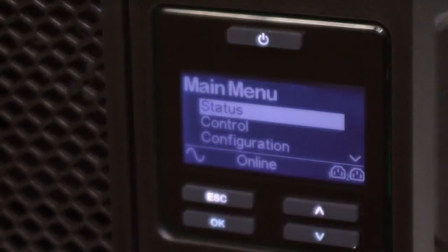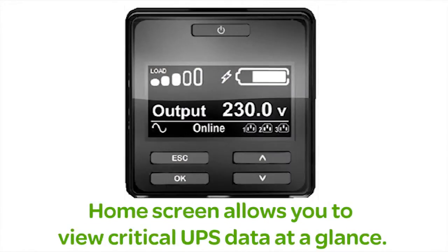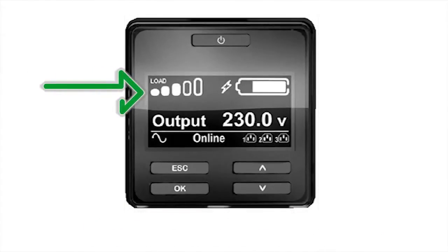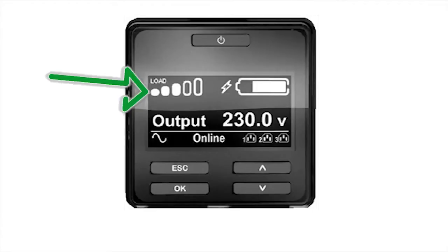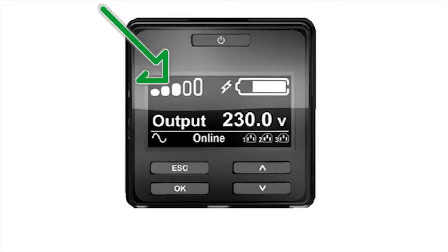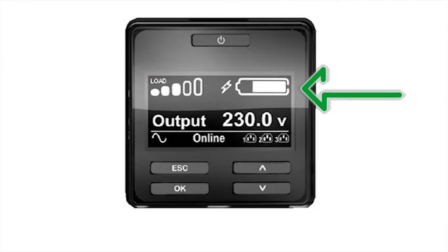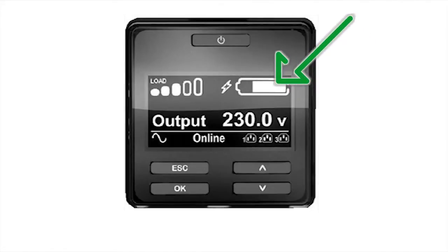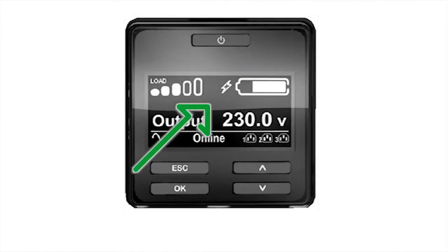Users can change any of the selected options once they've exited the setup wizard. The LCD status screen displays a wealth of valuable information. The load indicator displays present UPS load in relation to overall UPS capacity. The approximate load capacity percentage is indicated by the number of load bar sections illuminated — each bar represents 20% of the load capacity. The battery charge icon shows the state of battery charge, with the approximate charge indicated by the amount of the battery bar that is illuminated. A small charging icon will appear to the left of the icon when the battery is charging.